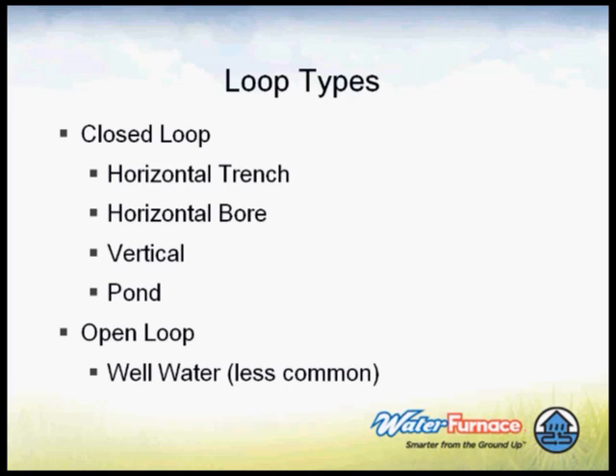Loop types: already mentioned the closed loop system. We have a horizontal trench loop - you dig a trench, normally 5 feet deep, lay the pipe in there, and fuse it all together at a header, so there's no possibility of leaks, and that's taken into the house. There's also horizontal boring, like utility companies use to run wires underground. A great benefit of horizontal boring is it doesn't damage the landscape nearly as much as the trench loop. A lot of times, like for farms, where they don't care as much, it's not forever - you just pile the earth back up on it and let it settle back down gradually over at least a couple of seasons. So that's the benefit of horizontal bore: you don't get everything torn up.